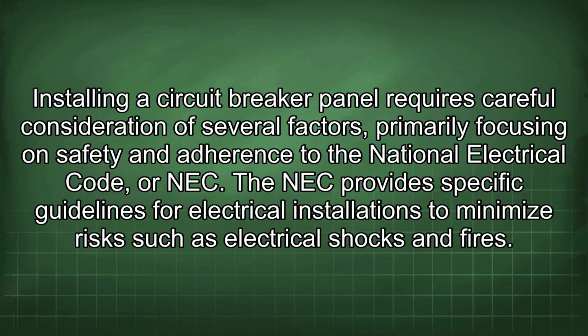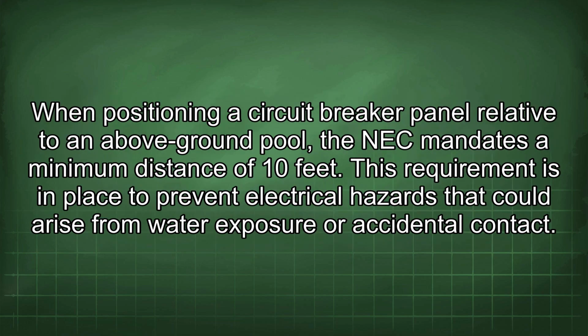Installing a circuit breaker panel requires careful consideration of several factors, primarily focusing on safety and adherence to the National Electrical Code, or NEC. The NEC provides specific guidelines for electrical installations to minimize risks such as electrical shocks and fires. When positioning a circuit breaker panel relative to an above-ground pool, the NEC mandates a minimum distance of 10 feet. This requirement is in place to prevent electrical hazards that could arise from water exposure or accidental contact.